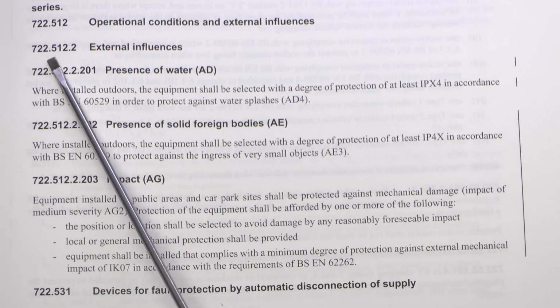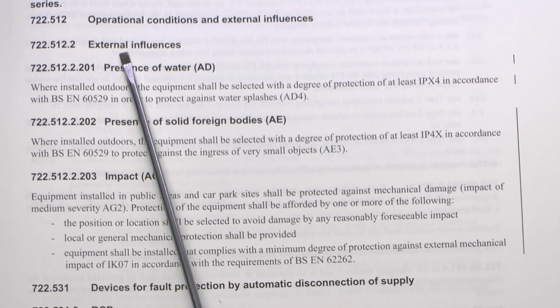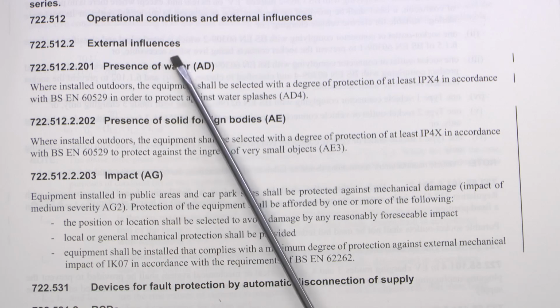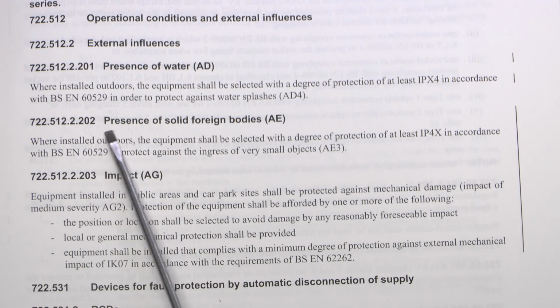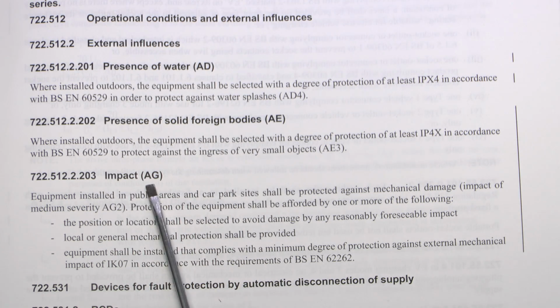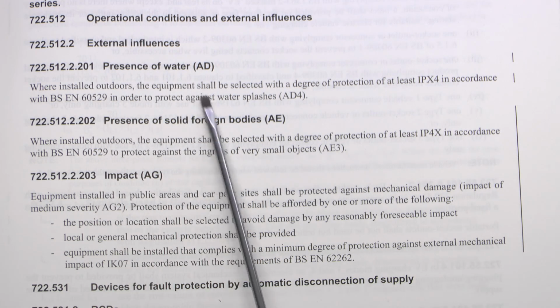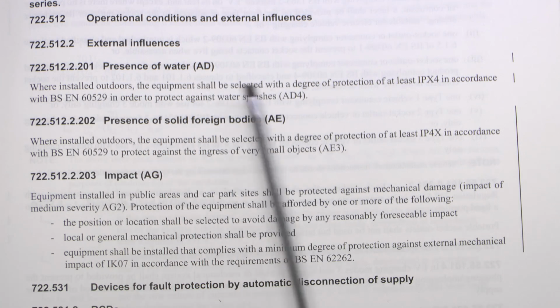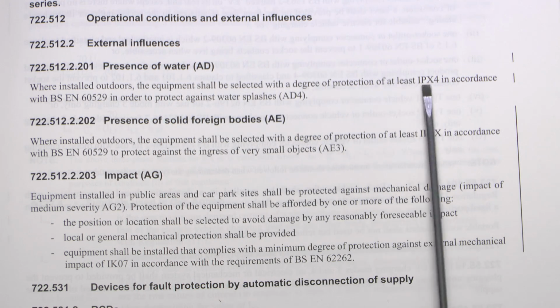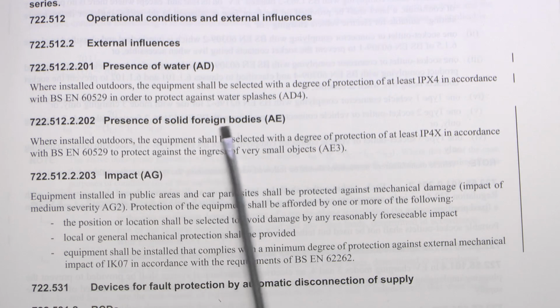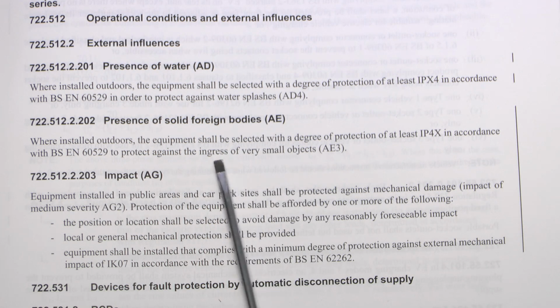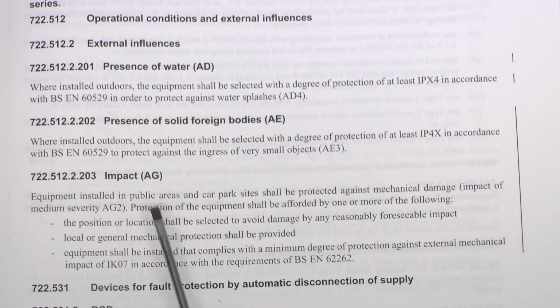This part here, 722.512.2, external influences. This has been expanded quite considerably, and we've now got these three individual items: presence of water, presence of solid foreign bodies, and impact. Previously, this entire bit just required a minimum of IP44 and nothing else, so now we've got a lot more detail. So essentially it's protecting against water splashes, which is what was in there previously, the IPX4 or 44 as it was earlier. And then we've got presence of solid foreign bodies, needs to be protected against ingress of very small objects to AE3, and impact, we've got a lengthy section here, up to impacts of medium severity AG2.